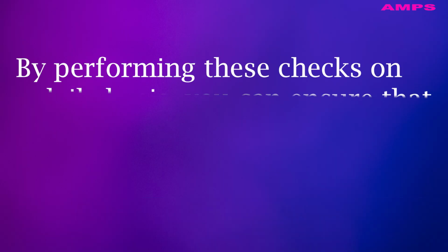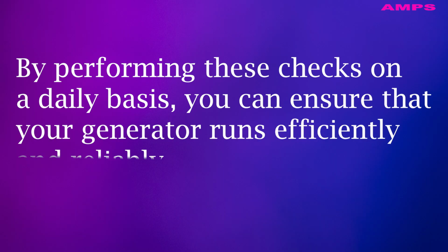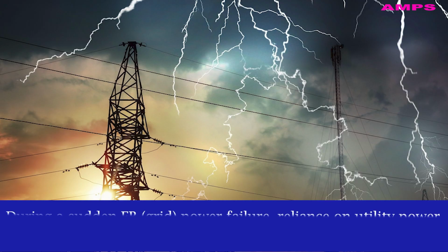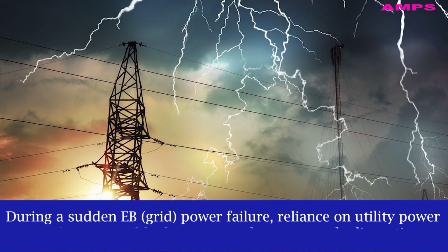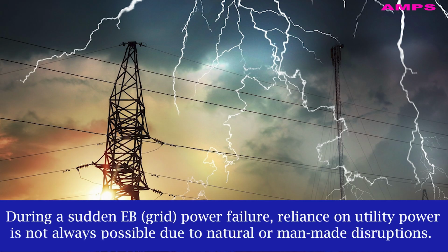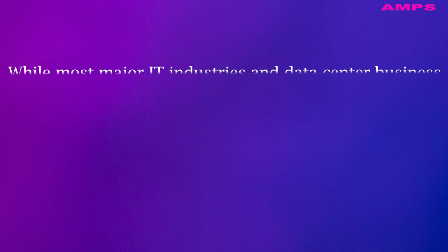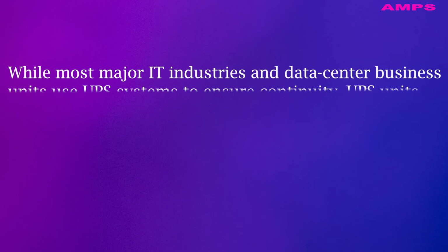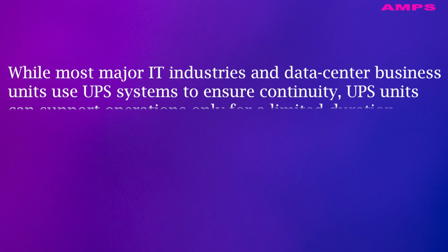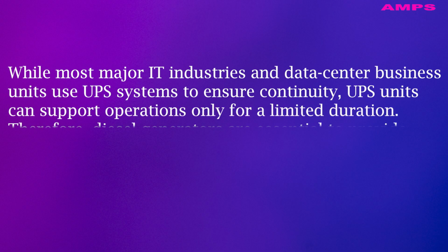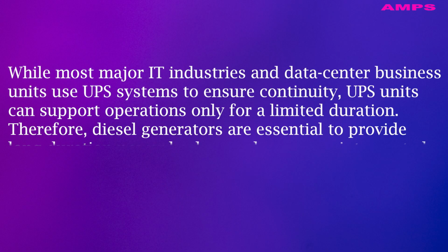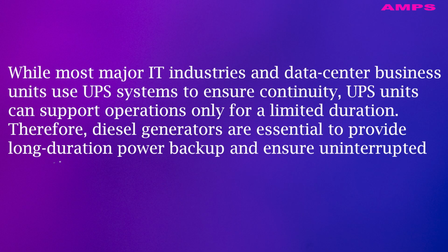By performing these checks on a daily basis, you can ensure that your generator runs efficiently and reliably. During a sudden EB, grid, power failure, reliance on utility power is not always possible due to natural or man-made disruptions. While most major IT industries and data center business units use UPS systems to ensure continuity, UPS units can support operations only for a limited duration. Therefore, diesel generators are essential to provide long-duration power backup and ensure uninterrupted operations.